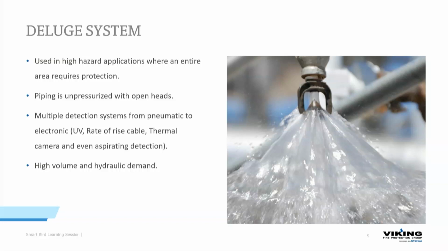Piping is unpressurized with open heads. Multiple detection systems can be used from pneumatic to electronic. Really depends on, are you outside, are you inside, are you in a dusty location? UV, rate of rise cables, thermal cameras, aspirating detection, they can all be used to trip a deluge valve, just depending on, like I said, what the actual environment is that you're having your deluge system in.